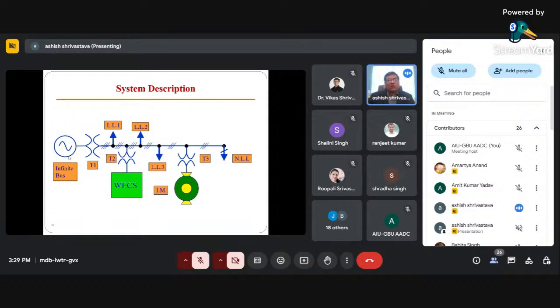So we need to ensure that while connecting these non-linear loads, the supply does not get polluted. From the source we should provide a clean voltage supply so that we can extract clean current, because whenever you connect a non-linear load, it will certainly draw a peaky current loaded with many harmonics, because of which your THD, total harmonic distortion, increases like anything. And as per IEEE 519, there is a limitation that for more than 10 ampere current, your THD must be less than 5%. So we need to ensure those international standards as well, whether it is the IEEE standard or the IEC standard we are talking about.